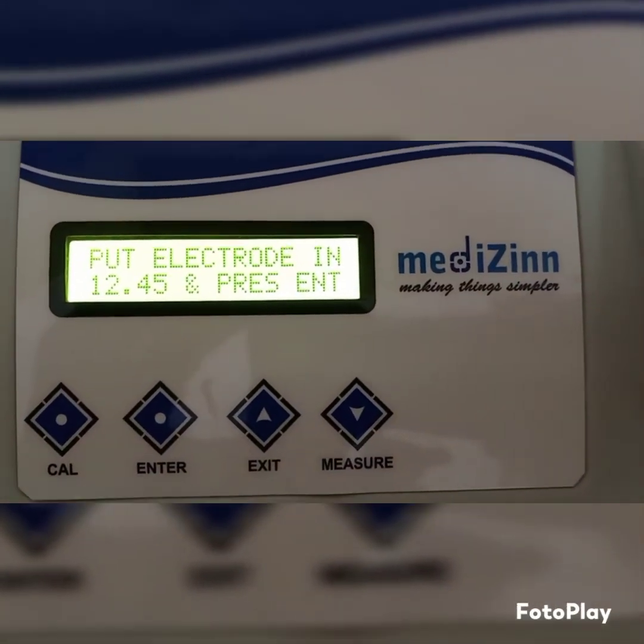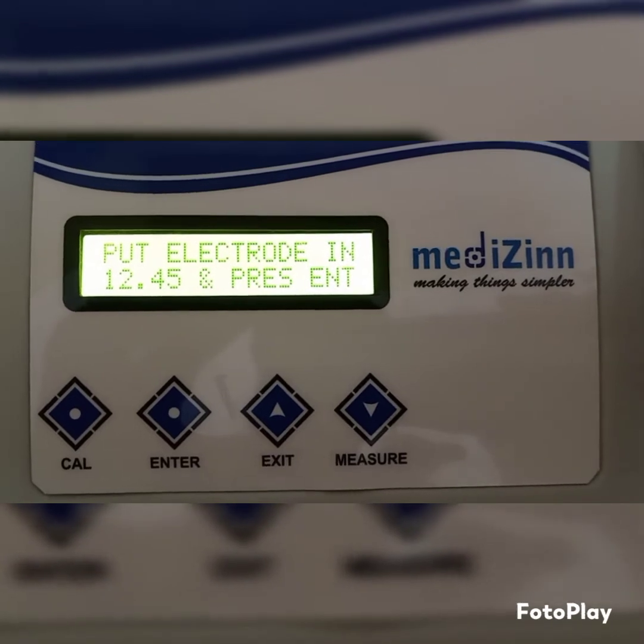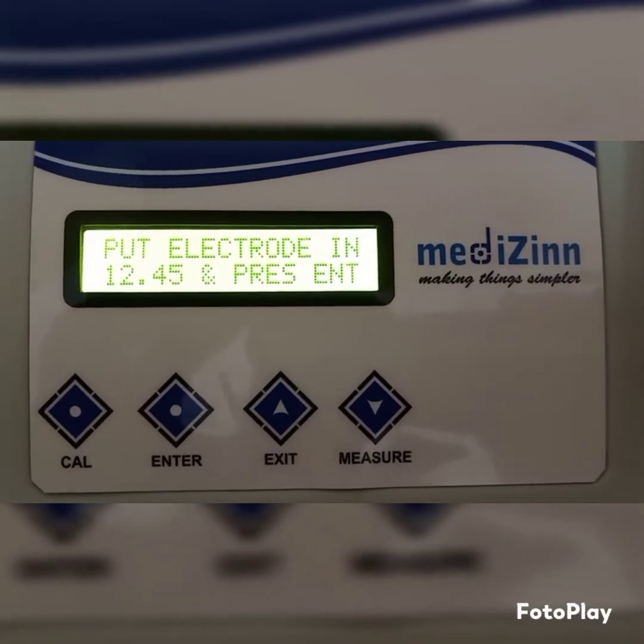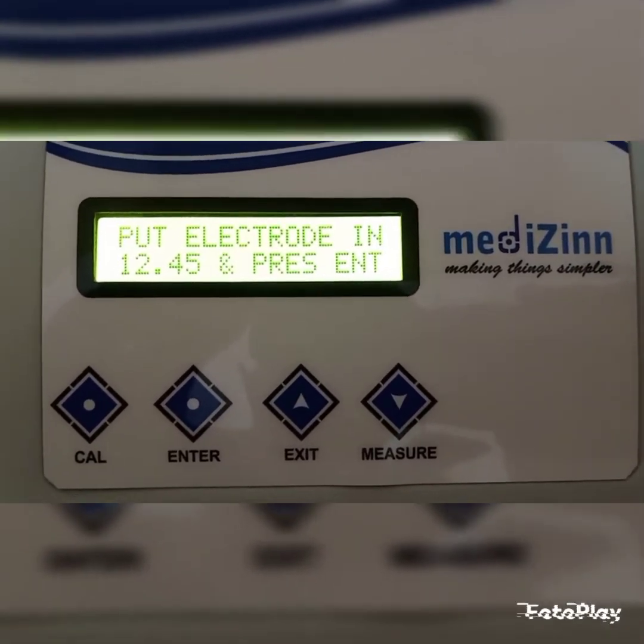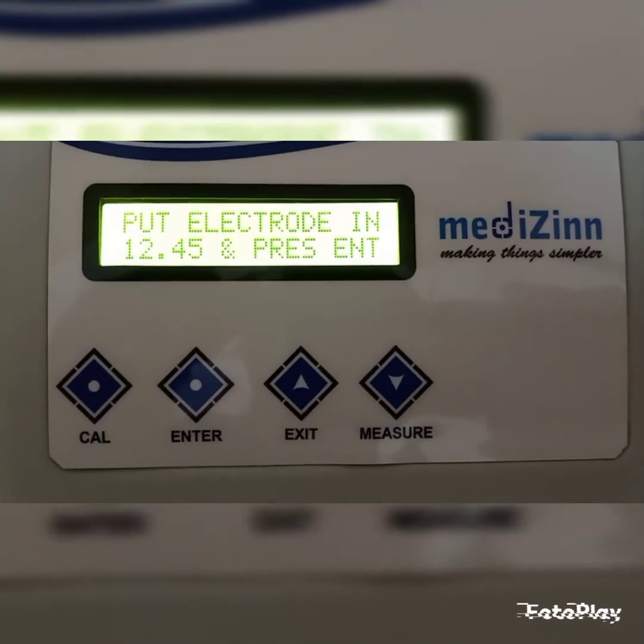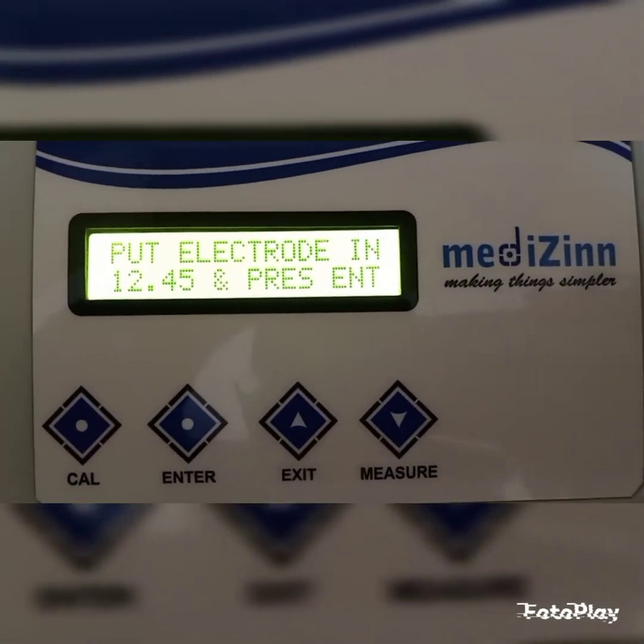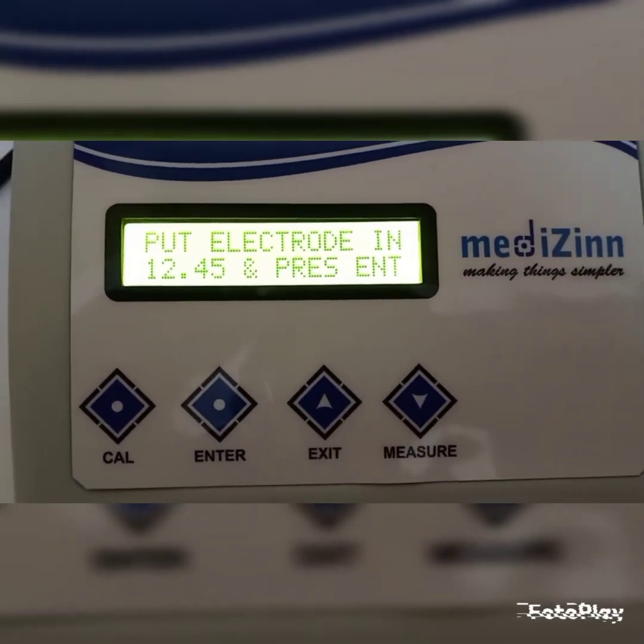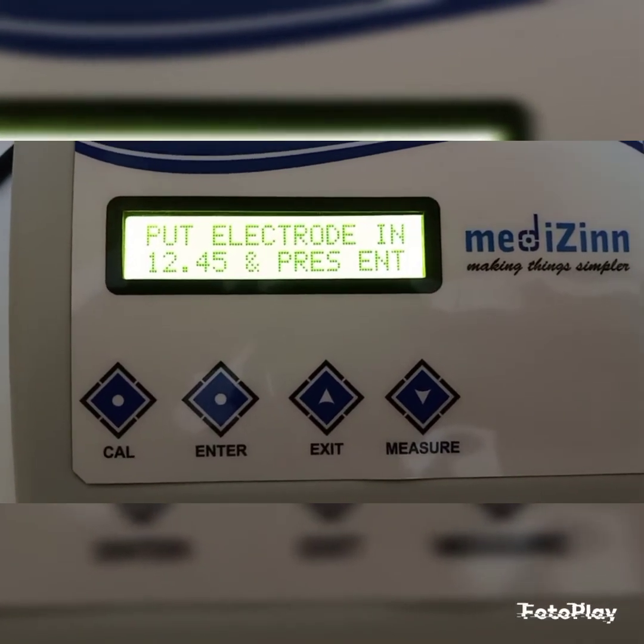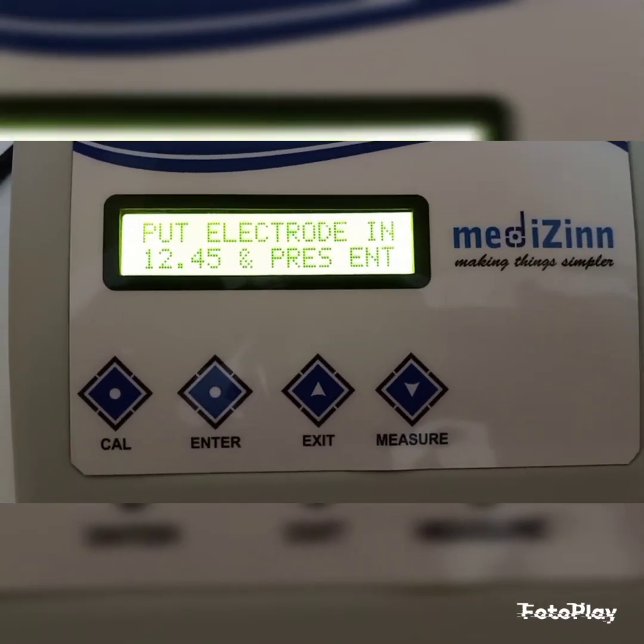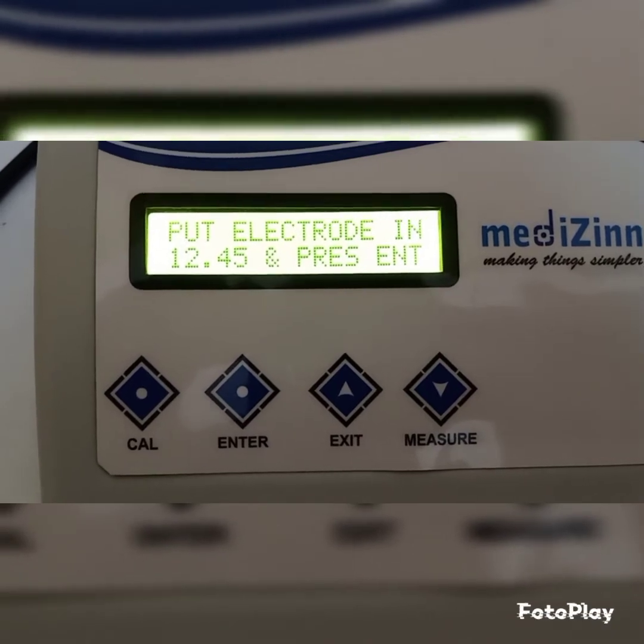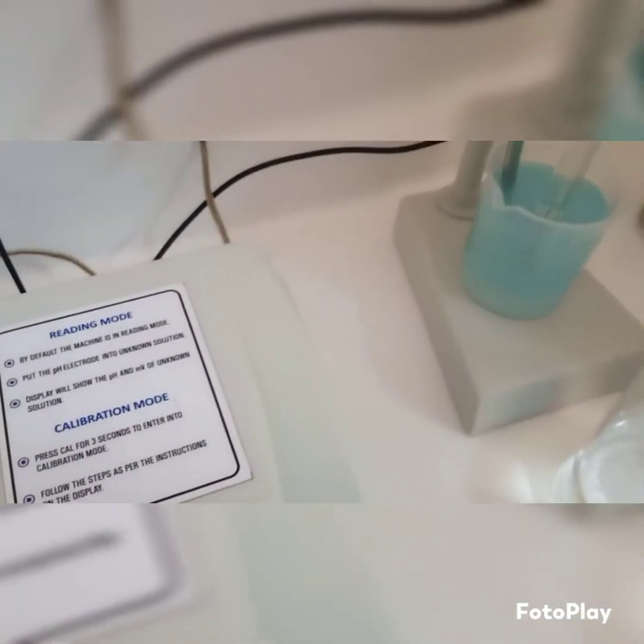9.2 pH buffer done. Now if you are performing 3-point calibration, then in that case when machine demanding 12.45, just press exit button. Now as we are going for a 5-point calibration, now put electrode into 12.45 and press enter. Again wash the electrode and temperature probe thoroughly using the distilled water and put both into 12.45 pH buffer.